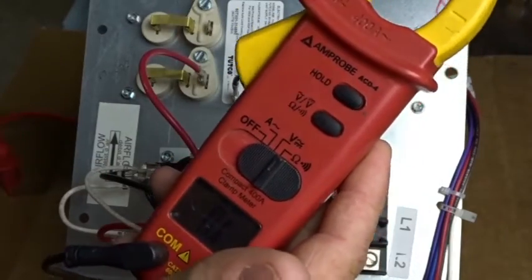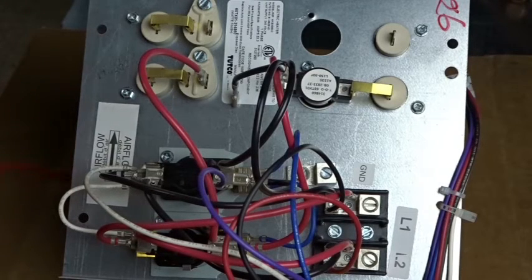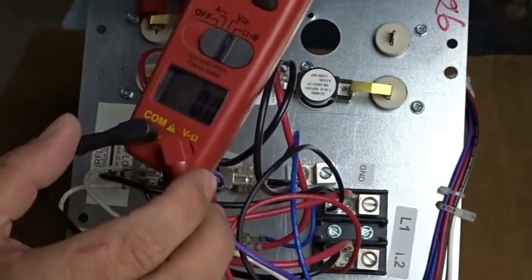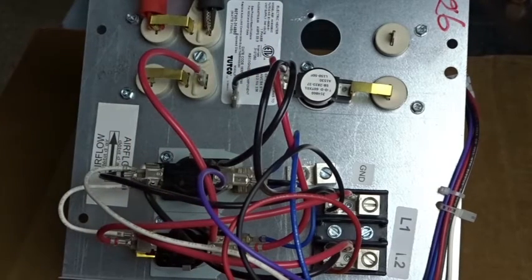I have the Amprobe ACD-4 here to check the resistance. I'm taking it down to the ohms setting. I'm going to put one clamp coming out of the element. I was testing to see if the Fieldpiece heads would work with this meter and they don't really work. And we have one coming out of the one-time fuse. And as you can see, we have zero resistance, which is exactly what we're supposed to have.